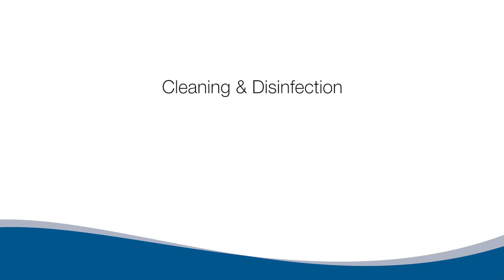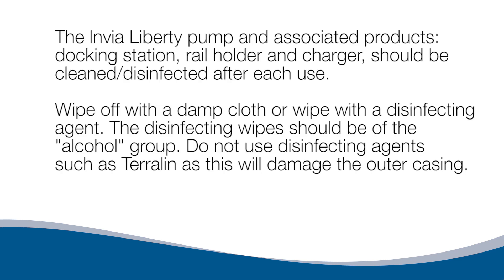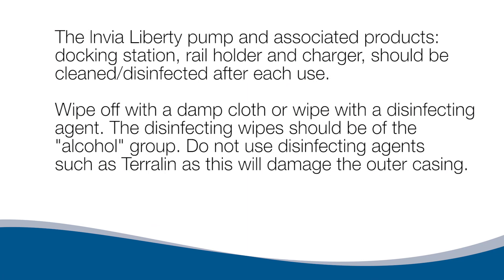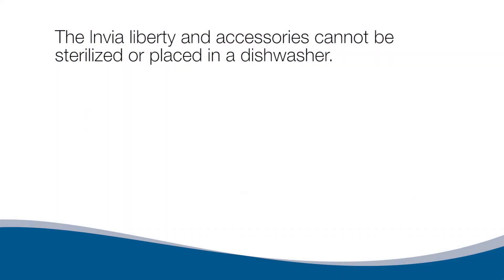Cleaning and Disinfection. The Invia Liberty pump and associated products — docking station, rail holder, and charger — should be cleaned and disinfected after each use. Wipe off with a damp cloth or wipe with a disinfecting agent. Disinfecting wipes should be of the alcohol group. Do not use disinfecting agents such as Terralin, as this will damage the outer casing. The Invia Liberty and accessories cannot be sterilized or placed in a dishwasher.